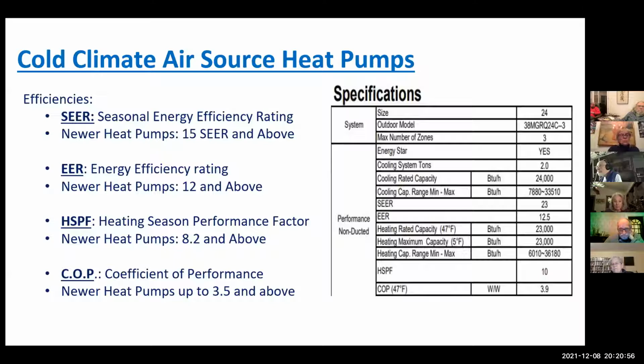The EER under it—you might see that for standalone air conditioners—and that rating isn't as useful I think, because it has a very specific criteria where it's only for a certain temperature, I believe 95 degrees, and a certain humidity level, and they just test the equipment at that one setting. So you might see it's only a 12 and think, wow, but that's for a very demanding condition. It doesn't give you an idea of how it operates over a whole spectrum, which is what you're going to want, because you'll use it throughout seasons and months.